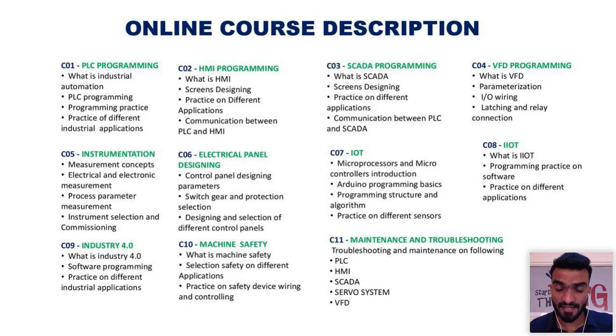How do you program field equipment or instruments? You need not program any field equipment. Your field instrument, whether it's a sensor or a limit switch, needs to be added to your PLC by means of hardware or a remote connection, so the field instrument is connected to the PLC, and you write the program into the PLC. So the program written inside the PLC controls or takes signals from your field instruments. You need not write any program to the field instrument itself; field instruments are connected to the PLC, which is the logical control, and then you make the programming as per the sequence required.